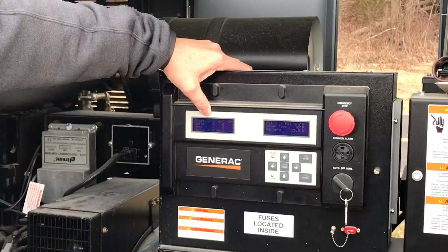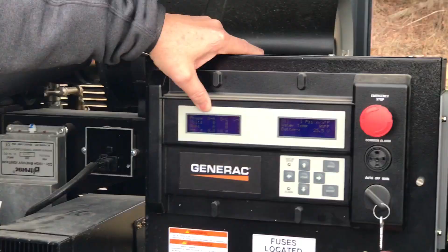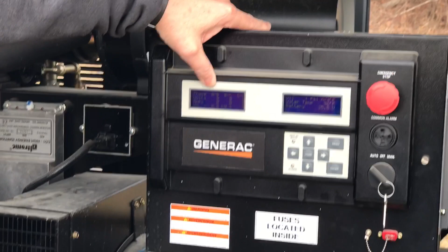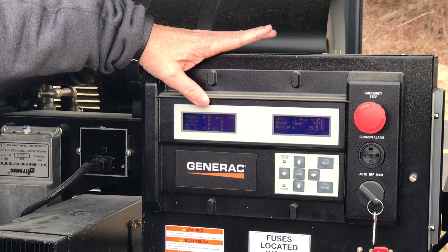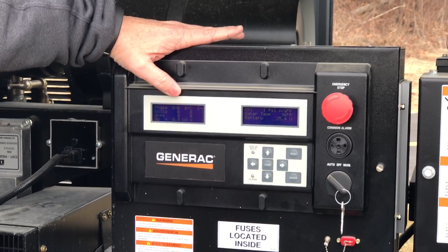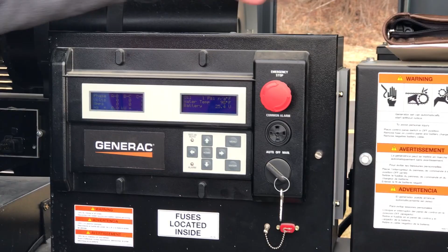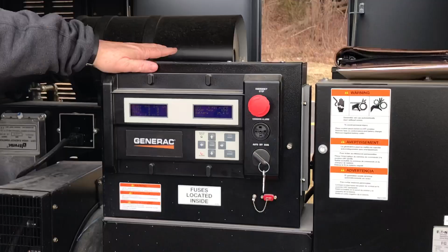On this screen here, if the unit's actually running, you'll see the volts per phase, and then if it has transferred over, you'll see the kW and the amps. It actually switched over. There's 250 amp breakers, one on either side of the control panel here, and they're just feeding two 200 amp transfer switches. Is that right? Okay. So, like I said, just a good visual check. Just make sure you open the door, make sure the water temperature is okay. Like I said, if it gets below zero, you may see that water temperature as low as 29 degrees or 30 degrees.